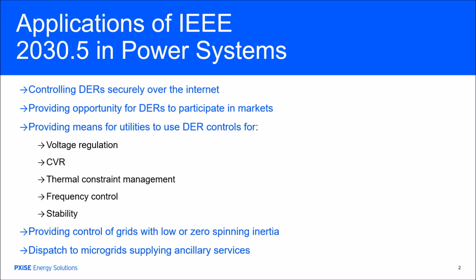Again, this is through the use of the meter mirror to provide data from the local facility to the server that can calculate what the control function should be and then issue real and reactive power commands back to the DERs. The same applies to thermal power management. We see in many cases, in particular Onslow is one as well, where we have to be aware when we make a dispatch to a DER that we don't cause an exceedance in the amperage capability of the lines that are connected to that DER.